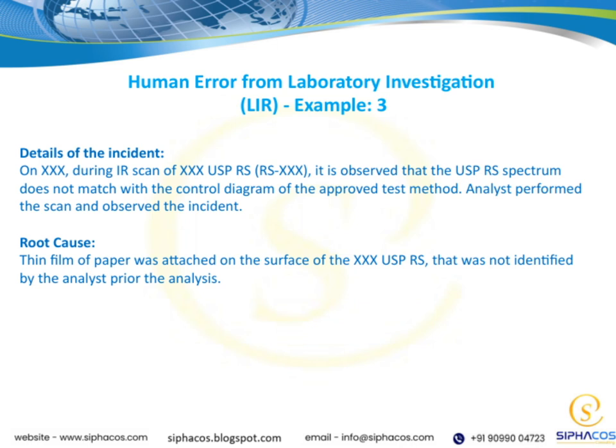The root cause of this issue was identified as a thin film of paper that was attached to the surface of the XXX USP RS. Importantly, this was something the analyst did not notice prior to starting the analysis. This small but significant oversight led to the spectrum mismatch.